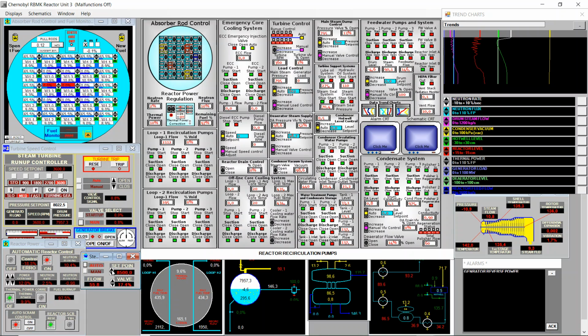And now let's increase the set point. Let's increase reactor power to 15%. And you see, even being at the main valve, I was close to 0, so we were still at risk of negative generated load because I was at too low a set point, I think. Now the valve is closed and the reactor power is at 15%, so we are increasing generated load now. Also, when we switch to main, it takes some time to open the main valve, while at the same time it's closing the startup valve, so you don't see the effect immediately.